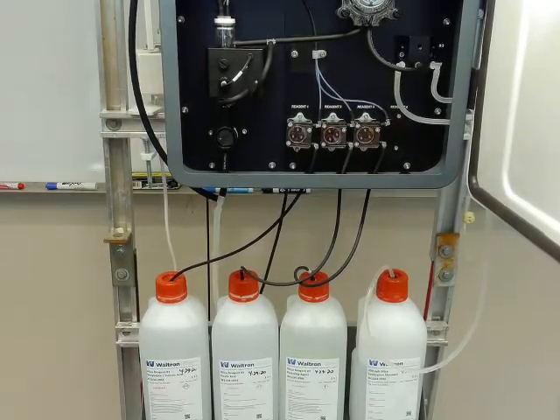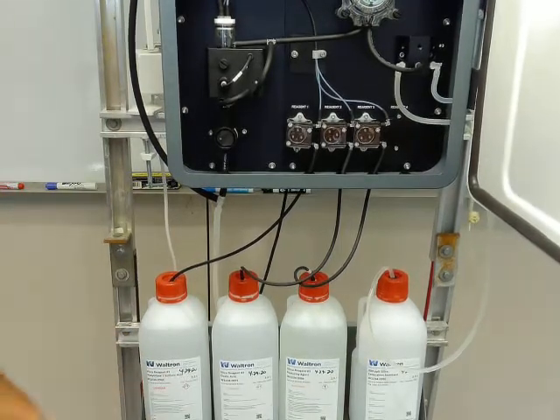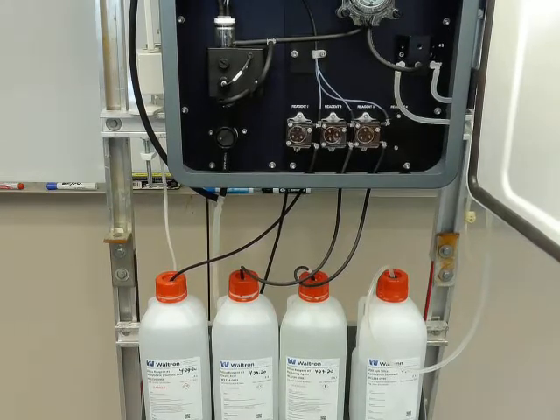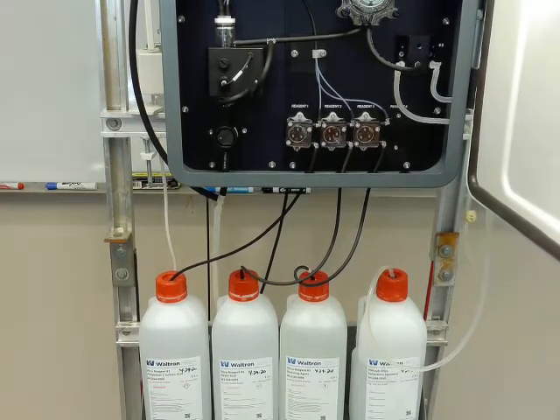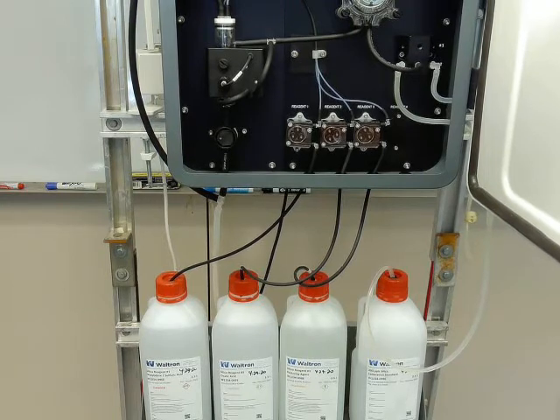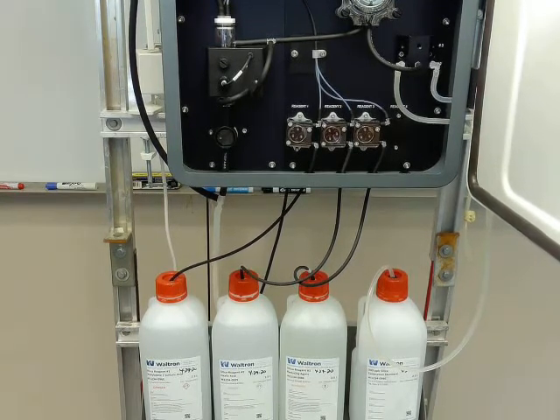Anytime you change your reagents, it's always a good idea to date code the reagent once it's opened. The shelf life on the reagents not only has a closed shelf life, but once you open them, they usually start to react with air a little bit. So it's always a good idea to know when you open them, just in case you end up in an extended shutdown or an offline period of time. The reagents don't sit for too long. It could cause cal failures and bad readings and things like that.